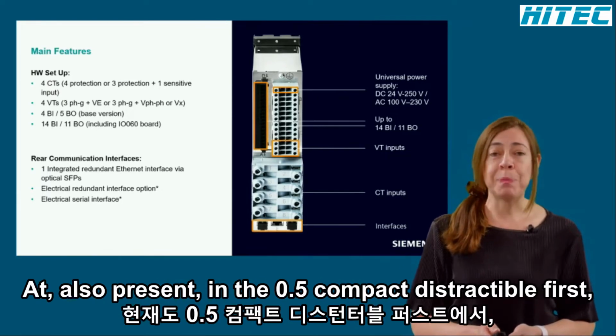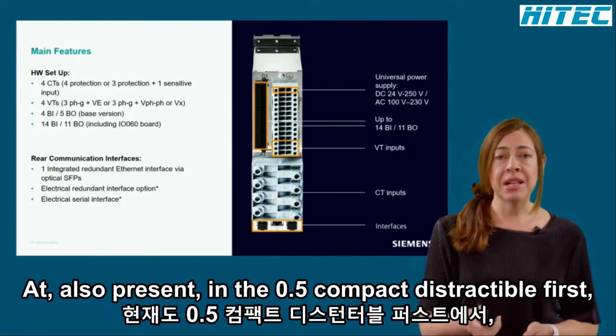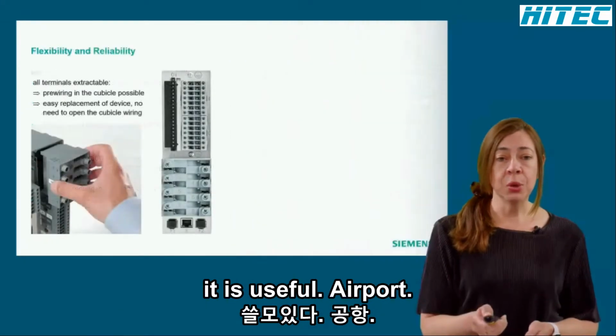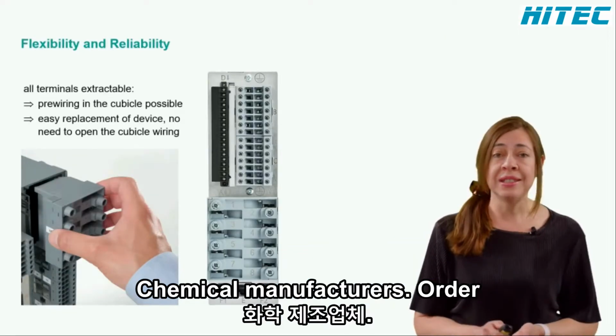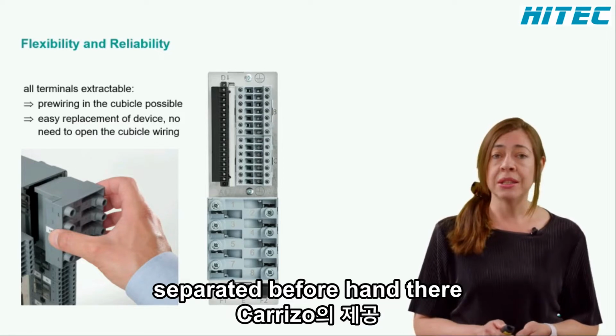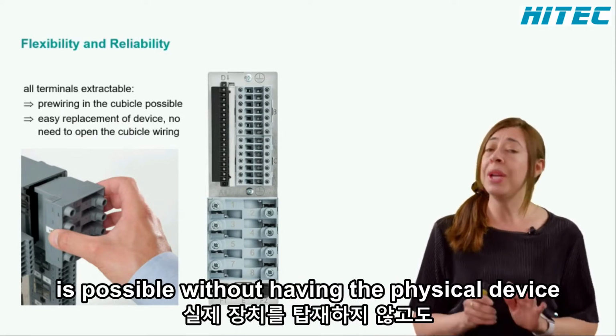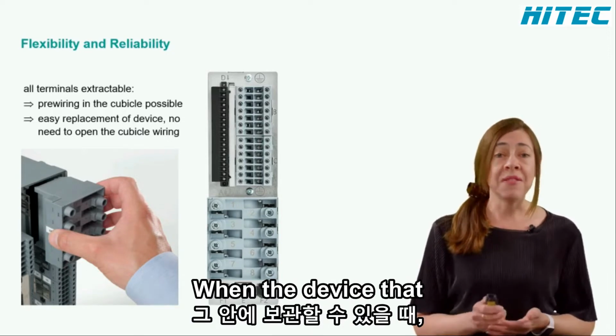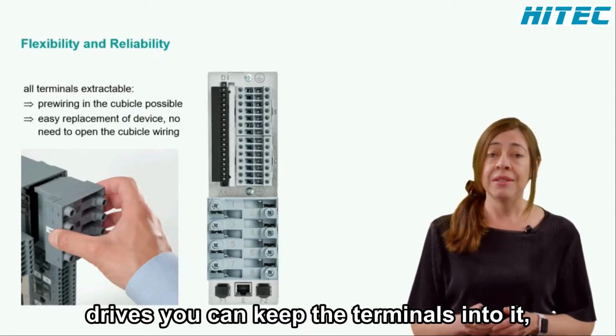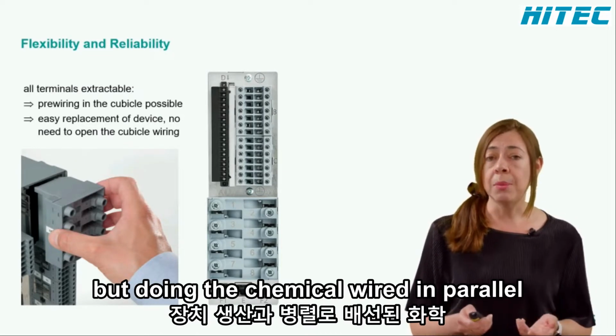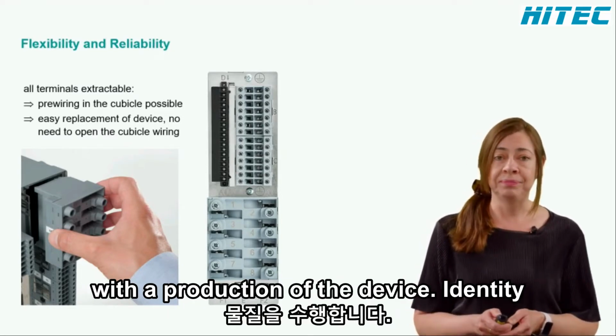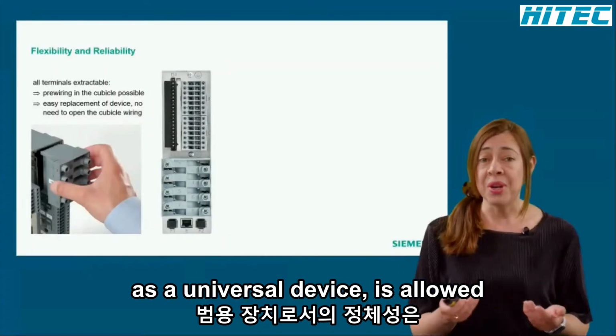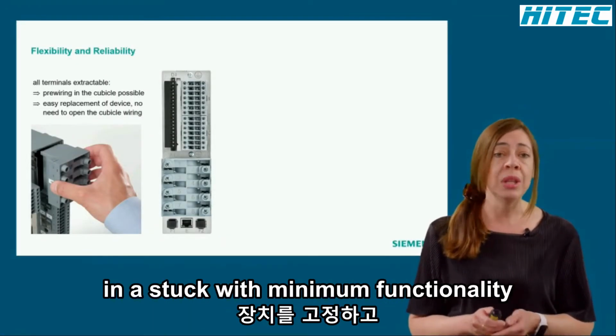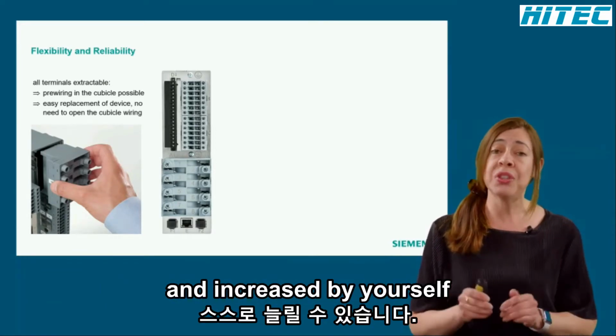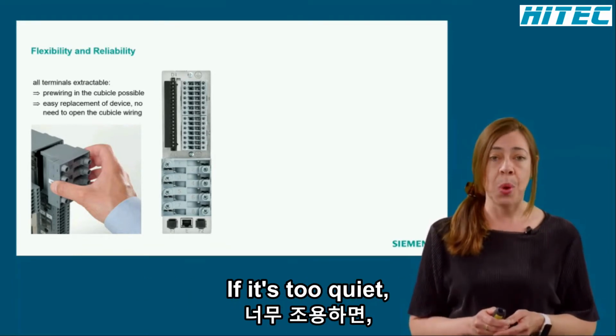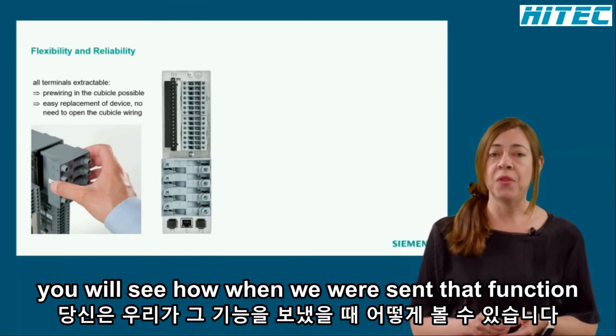Flexibility and reliability are also present in the SIPROTEC 5 Compact. All terminals are extractable. First, it is useful for manufacturers. Terminals can be ordered separately beforehand, therefore pre-wiring and testing of the cubicle is possible without having the physical device on board. When the device arrives, you can click the terminals into it. This reduces production times by doing the cubicle wiring in parallel with the production of the device. Alternatively, as a universal device, it allows you to have devices in stock with minimum functionality and increase that functionality yourself in the factory if it's required. You will see how when we present the function point manager.